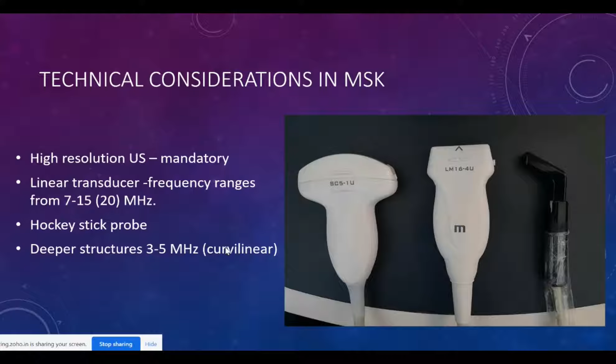Linear transducers are ideal for MSK since most of the structures are elongated or oval. It is the workhorse of MSK. The frequency range for the linear transducer starts from 15 megahertz, and now we have transducers which are more than 20 megahertz. There's the hockey stick probe, which can be used for smaller structures in hands.